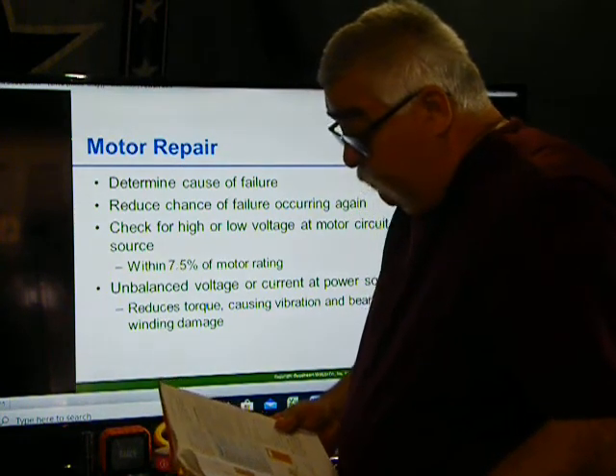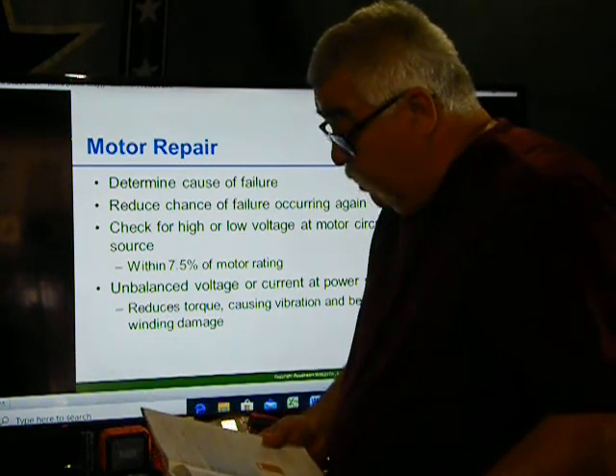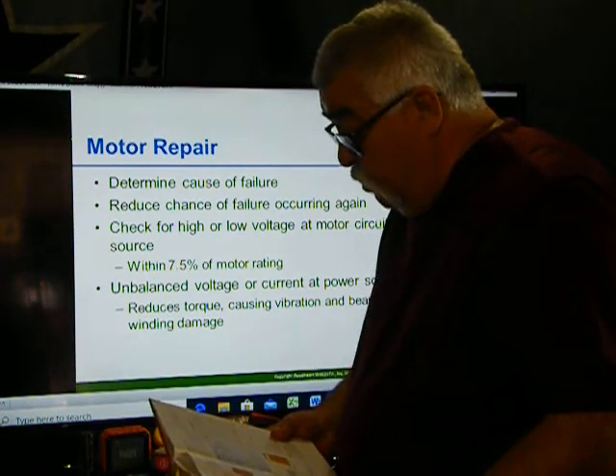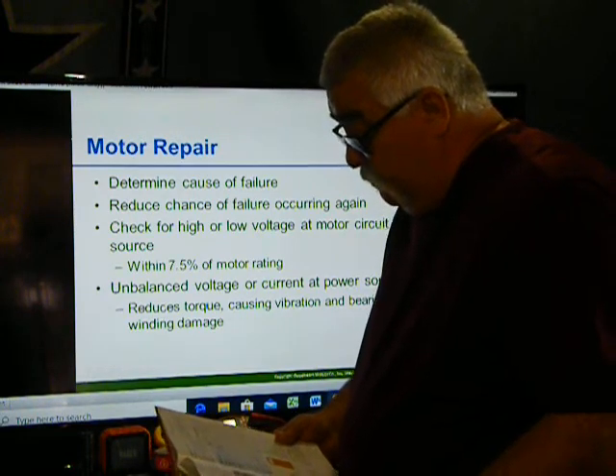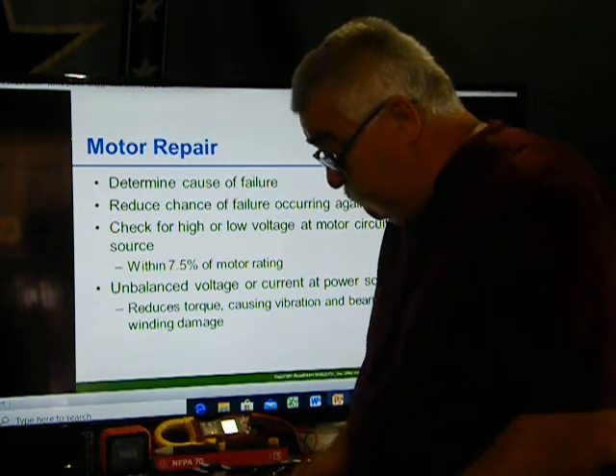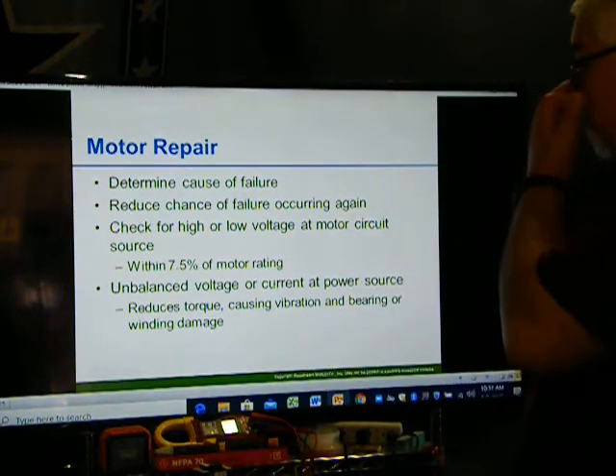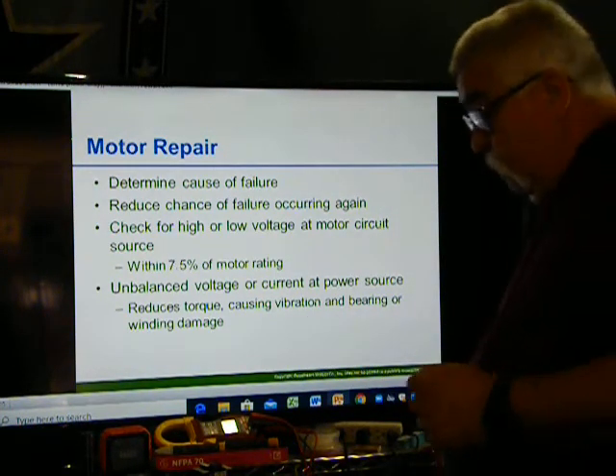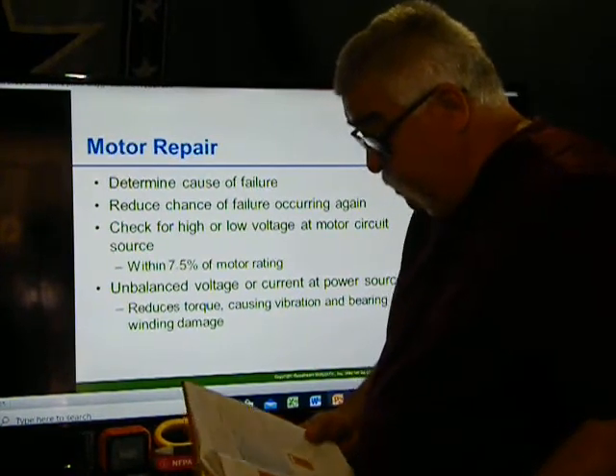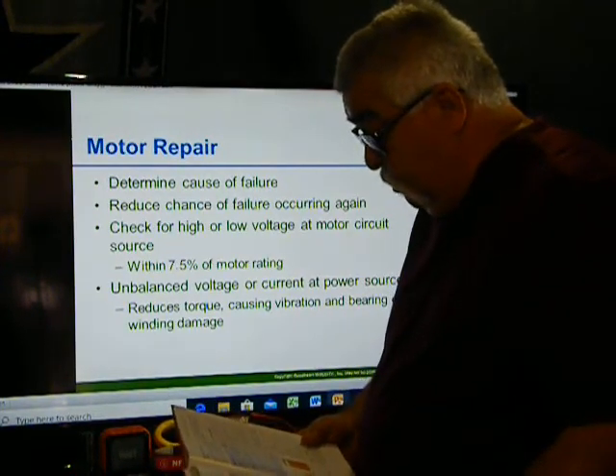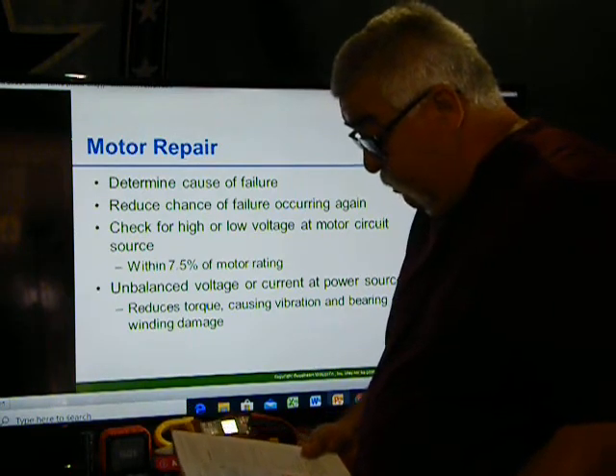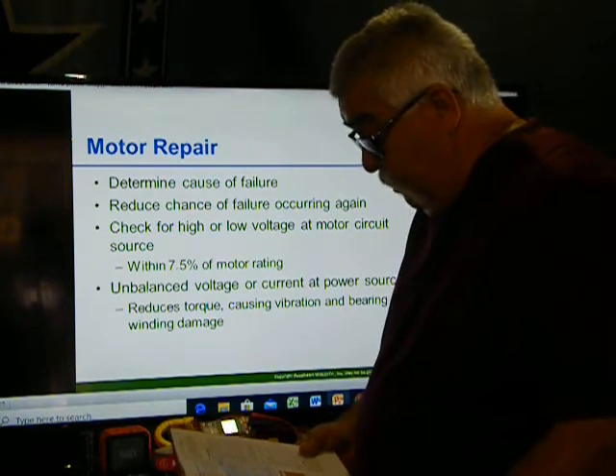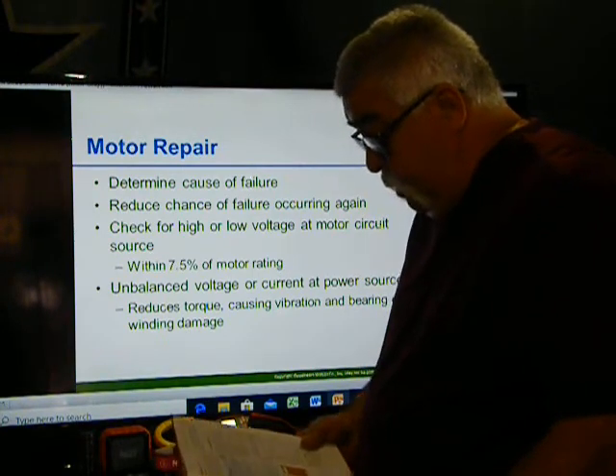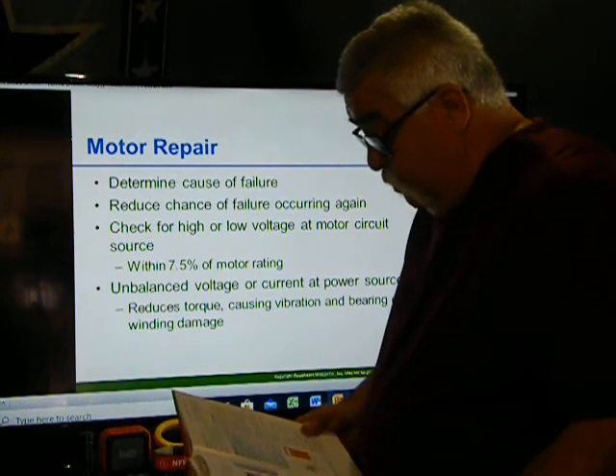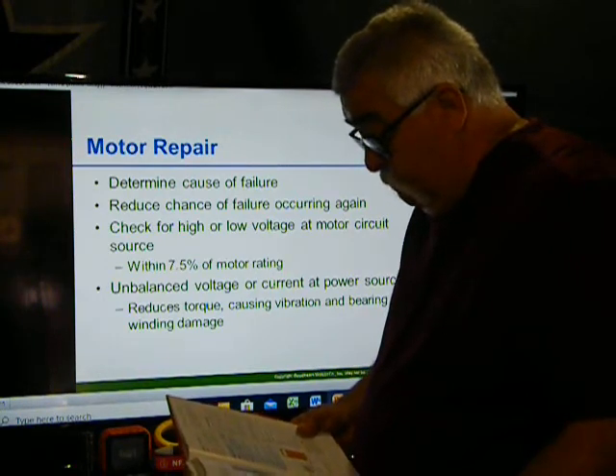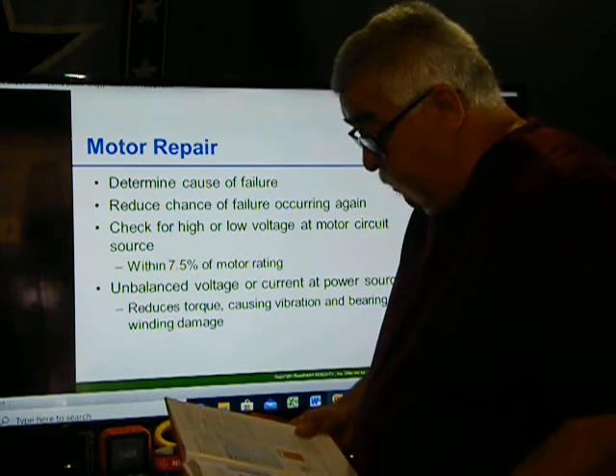Motors are generally the most expensive electrical equipment within commercial and light industrial operations. Motors are dependable and require only minimum maintenance. However, they eventually fail and must be repaired or replaced. Okay, so you have to determine the cause of failure. Here it says small defective motors are usually discarded and replaced with new ones. It costs less to replace a small motor than it does to repair it. Large motors are replaced to prevent downtime, and old motors are sent to the shop for repair. The repaired motor can be placed in service later.